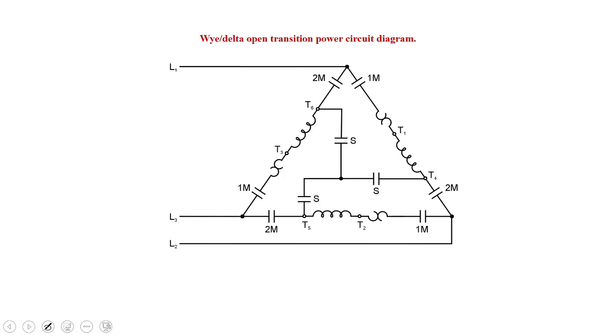Having a better look at what it looks like in delta here, we can recall the sequence of events. When we first pressed that start button, we saw that 1M contacts closed and the star contacts closed. So right now, these windings are connected in Y. When the timer timed out, the S contacts opened and the 2M contacts closed. Now it's connected in delta, with the overloads being in the phase. The overloads are in the phase, so Rule 28-306, sub Rule 2 applies to these overloads.